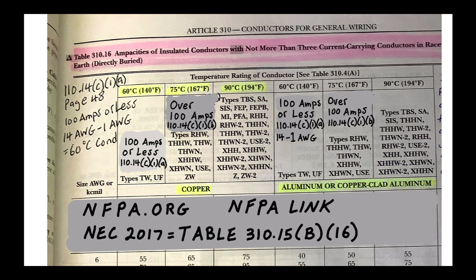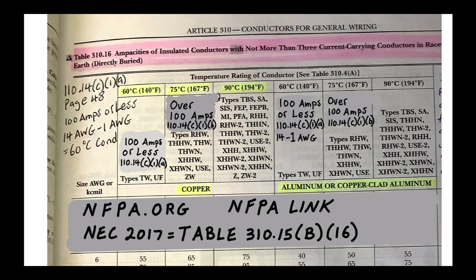I have notes reminding myself that for the 60°C column I need to check 110.14(C)(1)(a) — that's on page 48 in my code book — which applies to 100 amps or less. I'm also noting that conductors 14 AWG through 1 AWG fall under that 60°C rule.